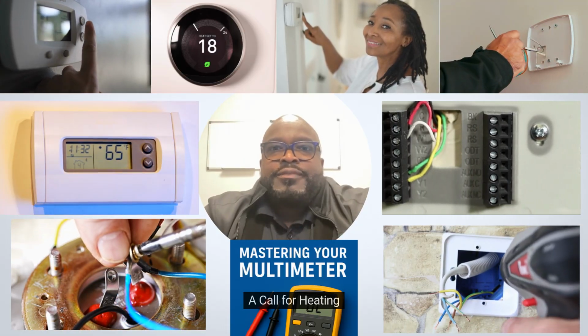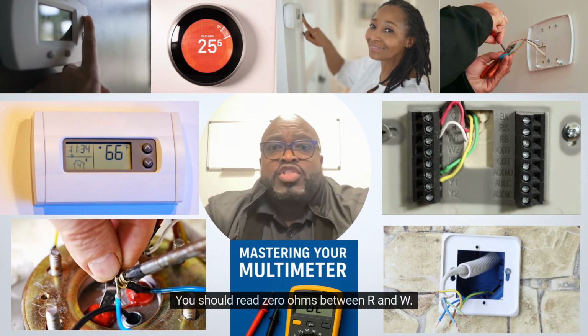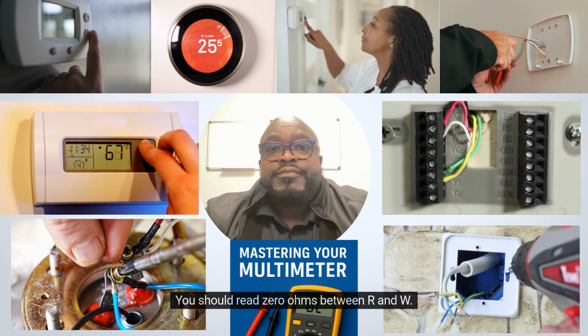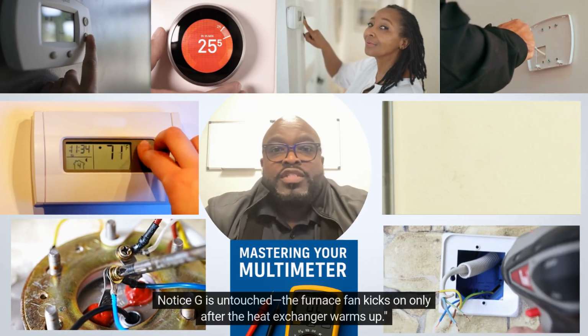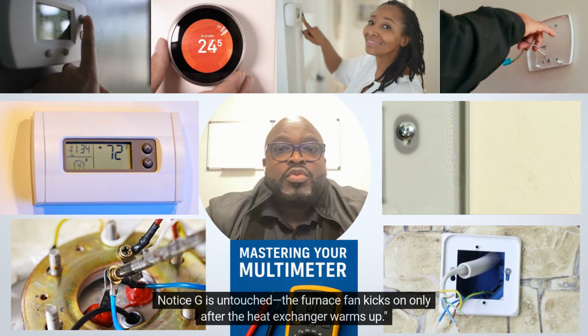A call for heating. Turn the stat to heat. You should read 0 ohms between R and W. Notice G is untouched. The furnace fan kicks on only after the heat exchanger warms up.